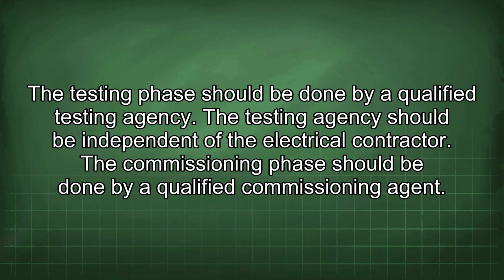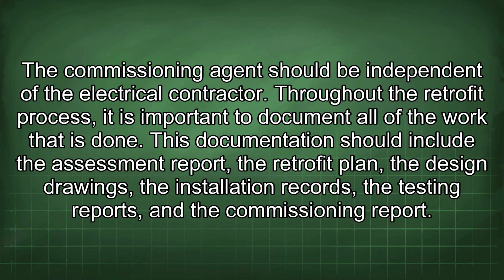The testing phase should be done by a qualified testing agency. The testing agency should be independent of the electrical contractor. The commissioning phase should be done by a qualified commissioning agent. The commissioning agent should be independent of the electrical contractor.